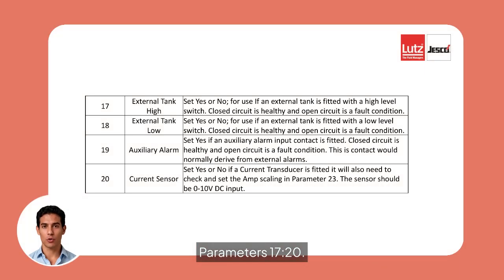Parameters 17 to 20 interface with external equipment. External tank high and low monitor remote storage levels. Auxiliary alarm allows an external fault input. The current sensor option enables monitoring of DC current via a transducer, improving protection against abnormal operating conditions.